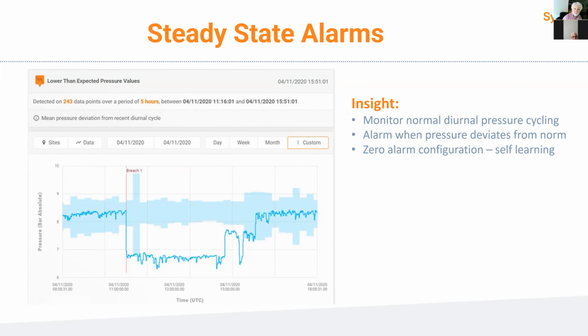And it's basically a zero configuration change monitoring tool. So once you've got 7 days of data, it's got enough history to learn roughly what the network should be doing at that location. And we set some upper and lower limits for each 15 minutes of the day and alarm if the current pressure deviates from those historic limits. And then it's a rolling system. So obviously, if a fault happens or you decide to change the operating pressure of the DMA, you'll get a step change. But after 7 days, it will have relearned the new normal. And those are tied in again to alarms via email out of radar and the API.